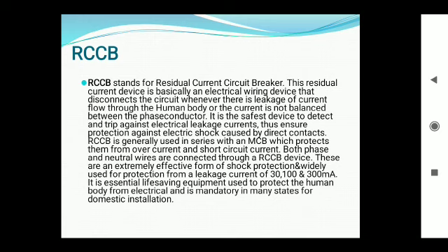An RCCB is generally used in series with an MCB, which protects against overcurrent and short circuit current. Both phase and neutral wire are connected through an RCCB device. These are extremely effective for shock protection and widely used for protection from a leakage current of 30, 100 and 300 milliampere. It is essential life-saving equipment used to protect the human body from electrical shock and is mandatory in many states for domestic installation.